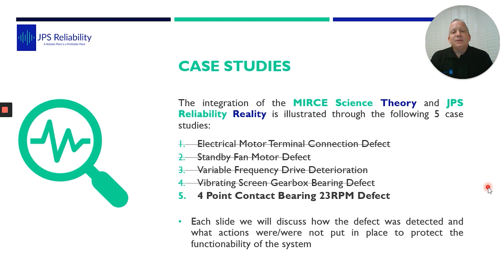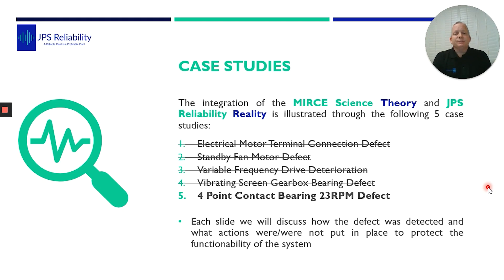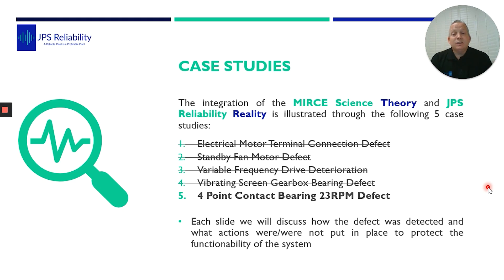Case study four was a vibrating screen gearbox — another great case study showing that if you use correct sampling and correct techniques, you can measure an inner race defect even in the harsh environments of a shaking screen. Today's case study is number five, on a four-point contact bearing rotating at 23 rpm, where the failure was detected before the functionality of the system was affected. These case studies are all featured in my book, Enhancing Reliability Through Vibration Technology.